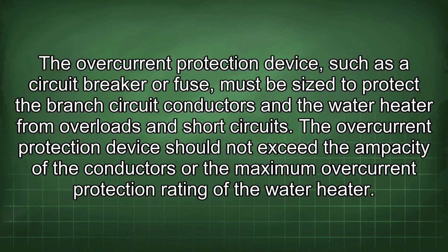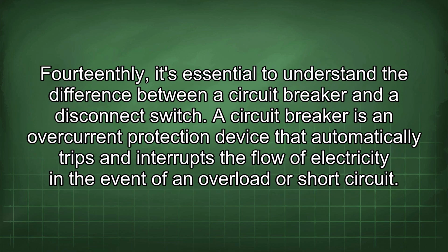The overcurrent protection device, such as a circuit breaker or fuse, must be sized to protect the branch circuit conductors and the water heater from overloads and short circuits. The overcurrent protection device should not exceed the ampacity of the conductors or the maximum overcurrent protection rating of the water heater. 14thly, it's essential to understand the difference between a circuit breaker and a disconnect switch.